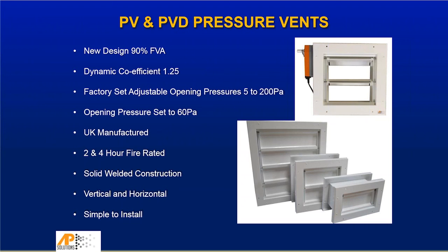We sometimes get customers turning around and saying, when we cover the pressure vent over, we get a 10-minute hold time. When we don't, we're getting 9.5. What we tend to find there is that there are holes in integrity that haven't been sealed up properly within the room. And once a company that understands room sealing is involved, there never is a problem.